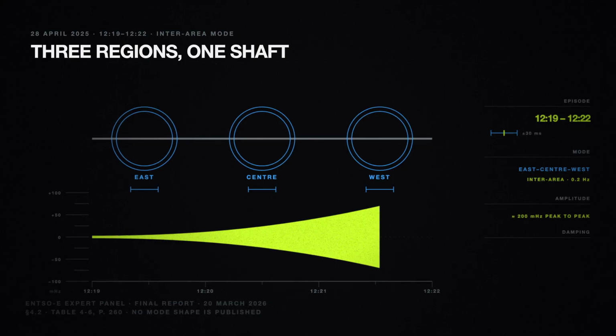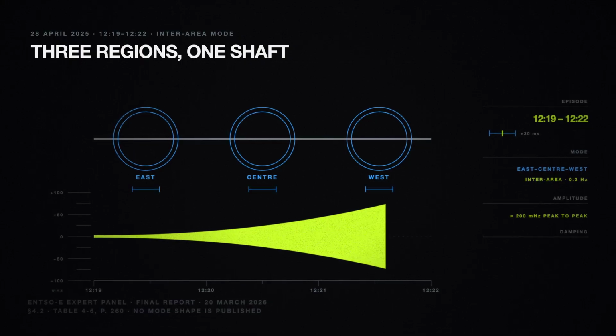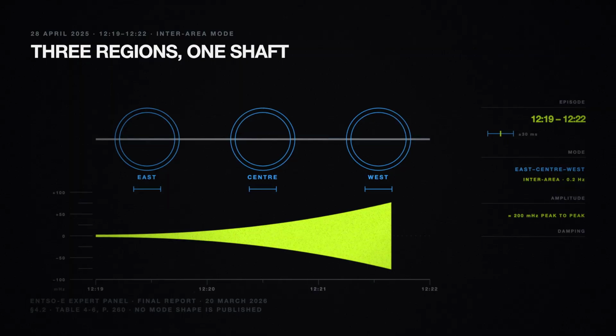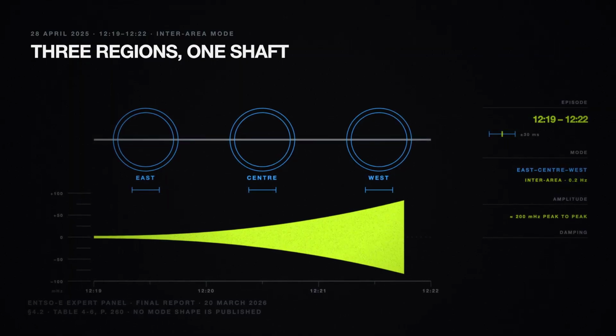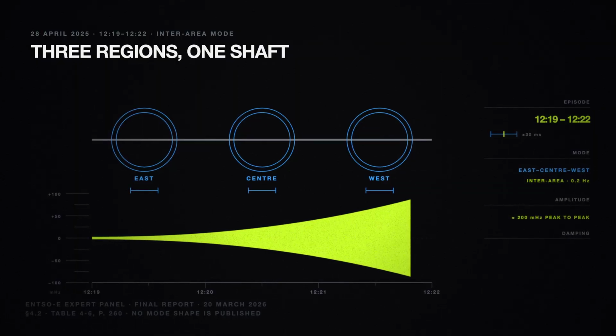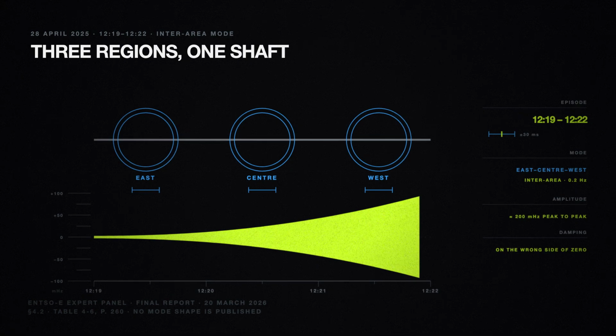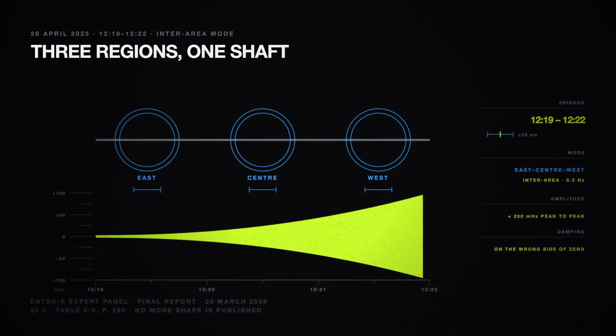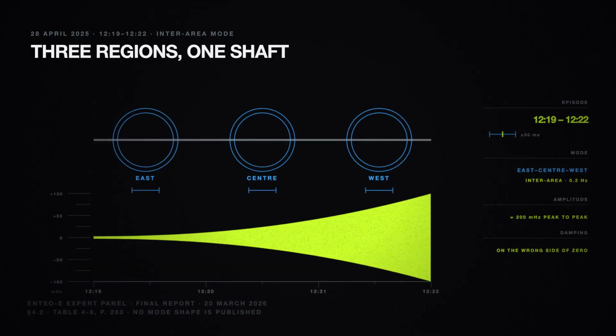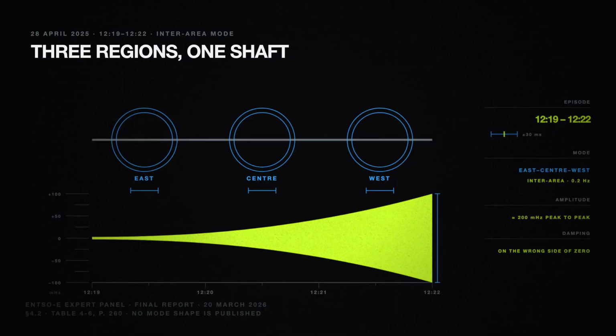An oscillation that a system is holding down loses a little of itself on every cycle and shrinks. That is what damping is, and it is measured as a percentage. This one had damping on the wrong side of zero. Negative damping does not settle and does not shrink. Every cycle comes back larger than the one before it. The mitigation measures that morning eventually stopped the growth. They did not reverse it. For 3 minutes, it did not settle.